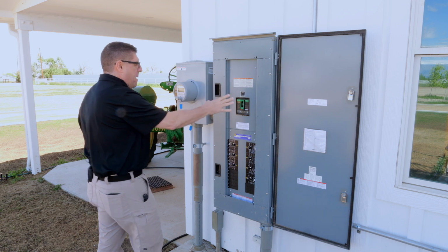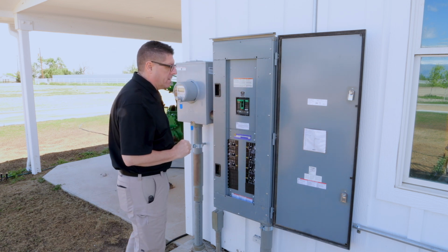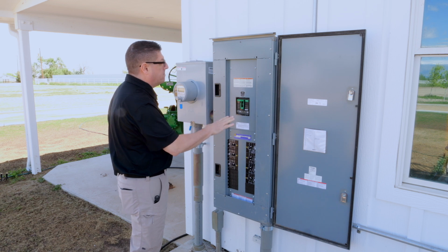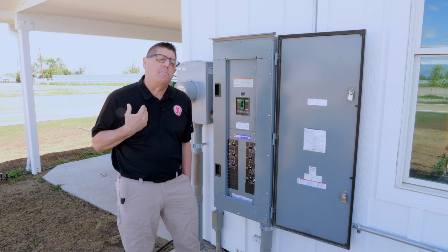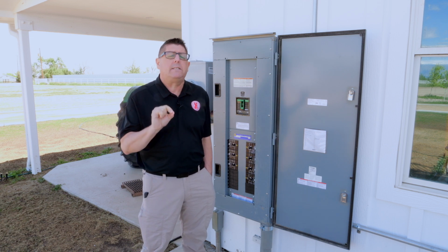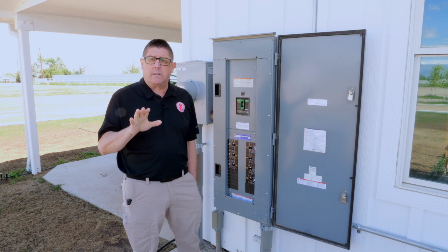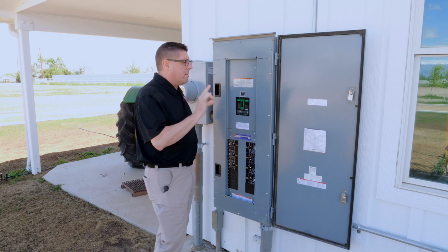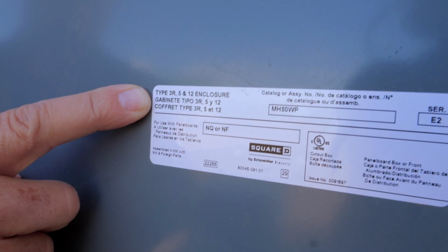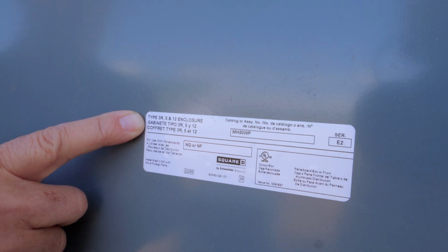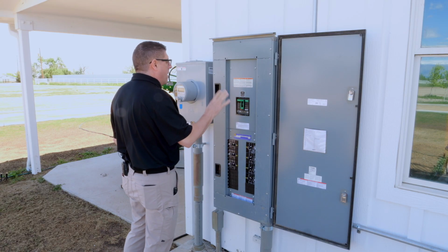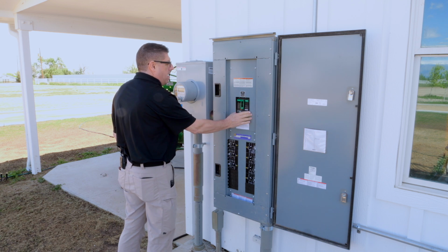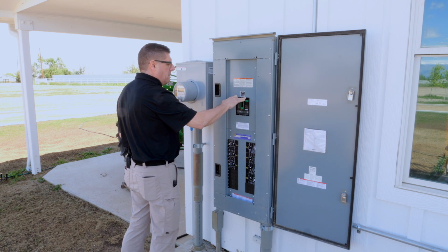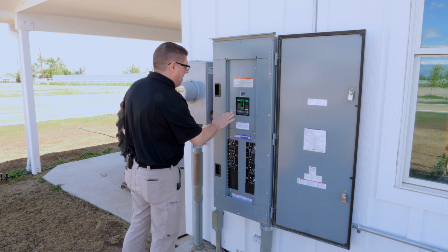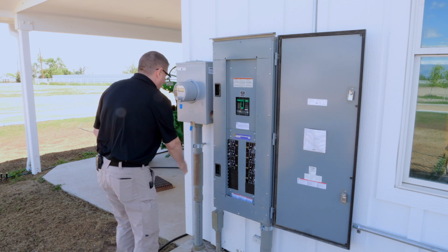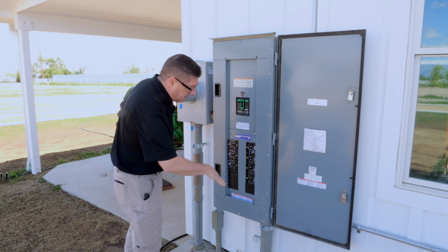Now, when I'm looking inside of the panel, I'm looking for any physical damage. That could be burn marks, that could be rust marks. Since we are on the outside of the building, I also want to verify that this is at least a Type 3 panel. I'll know it's a Type 3 panel by looking at the panel number and rating on the label plate itself. Now, I'm going to determine where my service disconnect is. That's right here. It says main or principal, or it will say service disconnect. That's what's servicing through this meter and going into the building.